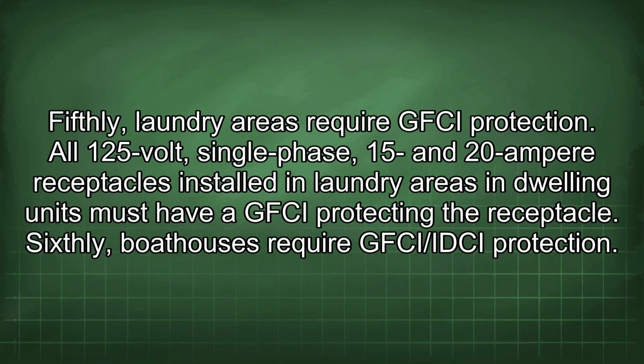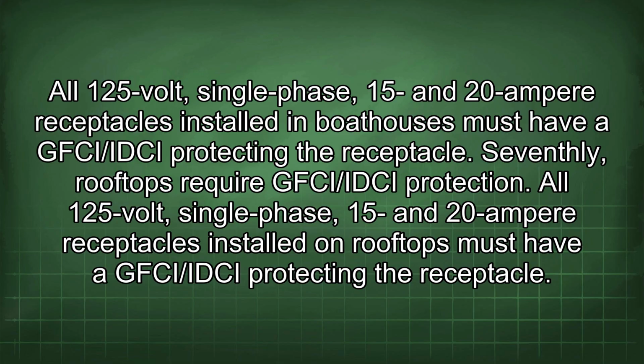Fifthly, laundry areas require GFCI protection. All 125-volt, single-phase, 15 and 20 ampere receptacles installed in laundry areas in dwelling units must have a GFCI protecting the receptacle. Sixthly, boathouses require GFCI/IDCI protection. All 125-volt, single-phase, 15 and 20 ampere receptacles installed in boathouses must have a GFCI/IDCI protecting the receptacle. Seventhly, rooftops require GFCI/IDCI protection. All 125-volt, single-phase, 15 and 20 ampere receptacles installed on rooftops must have a GFCI/IDCI protecting the receptacle.